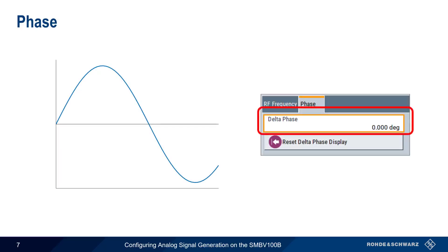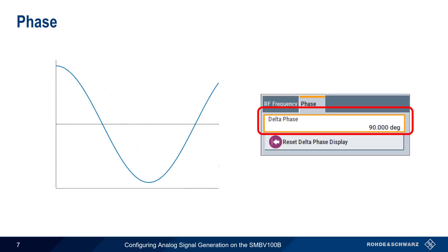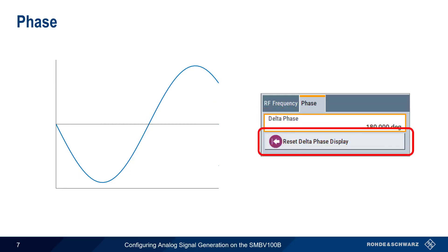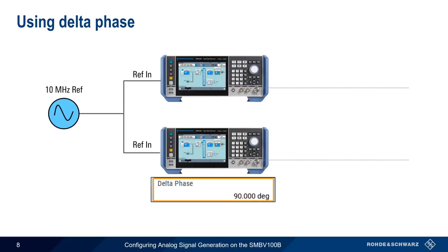Signals transmitted by the SMBV normally have a 0 degree initial angle. If we want to shift this initial phase angle, this can be done using the Delta Phase settings. For example, we can set the initial phase to 45 degrees, 90 degrees, 180 degrees, etc. We can also use the Reset Delta Phase display to use the current phase as the reference value. The Delta Phase setting is particularly useful if a common reference signal is shared between multiple instruments or DUTs. For example, Delta Phase could be used to create a 90 degree phase difference between the signals from two different generators.